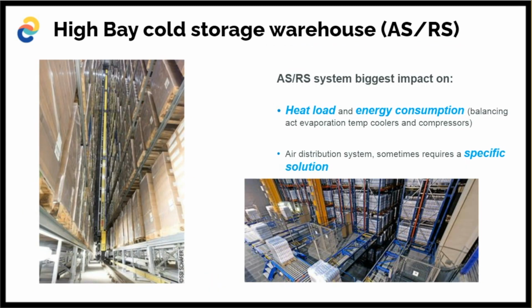So now you see here on the left this big crane, and that is what an ASRS system generally looks like. It's a big crane or cranes, maybe 4 or 5 in one room, going up and down, and back and forth all the time. And therefore, it has an impact on our air distribution, but also on our heat loads. So the heat load calculation should take these big cranes into account. And in terms of energy consumption, we have to have a very narrow balancing act between the evaporation temperature of the coolers and the compressors. And sometimes this air distribution system requires a specific solution.